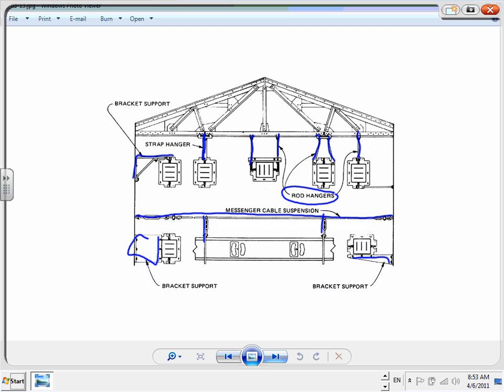If you are to work on a project that has a busway, the first thing you need to do is talk to the structural engineer. The first thing. Because you're going to hang this heavy equipment, 2,000, 3,000 amp bus duct, from the structure of the building. Would the structure handle a 4,000 or 3,000 amp bus duct hanging from it? That's a question you have to talk to the structural engineer about. You can't just go hang a heavy load directly from the ceiling if that structure is not rated. Look at the structure. All this, guys, is mechanical, physical load on these trusses. You have at least to consult with the structural engineer, load-wise. At least mention that to them, especially if you have a 2,000, 3,000, 4,000 amp busway that you need to hang from the ceiling. The rest of it is hardware.